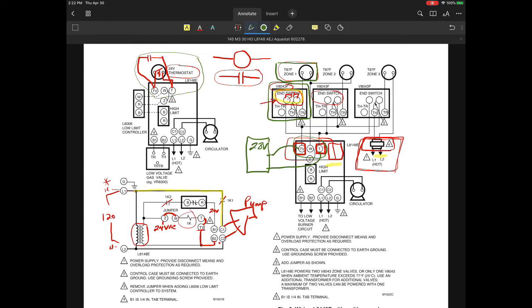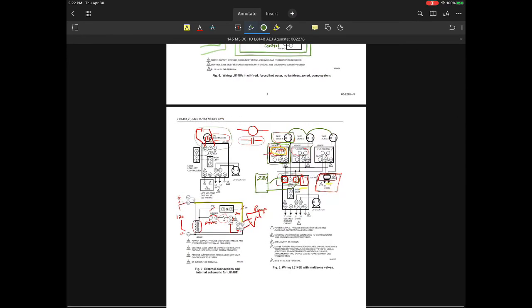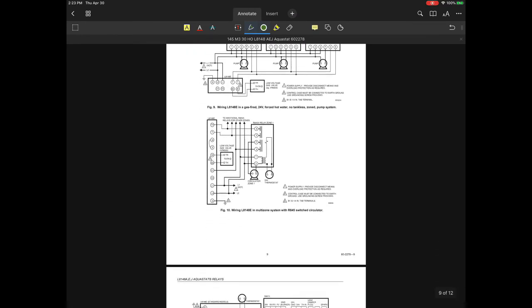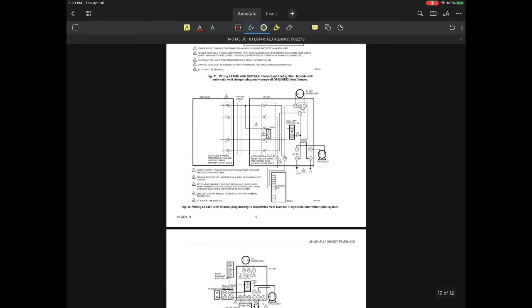And I point that out simply because every one of the Aquastats in the field is going to say 24-volt thermostat. And if you're not familiar with hydronic systems, you might think you have to bring each thermostat from all the zones directly to the Aquastat. That's not what they are intending to do. So electrically, we're just saying we need isolated sets of contacts. And obviously you cannot parallel three. You can't do zone 1, zone 2, and zone 3 in parallel. If you did that, anytime you'd have one of those call, you'd have thermostat 1, zone valve 1, zone valve 2, and zone valve 3.